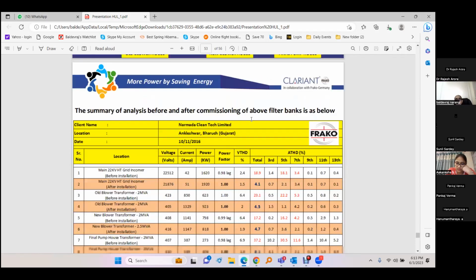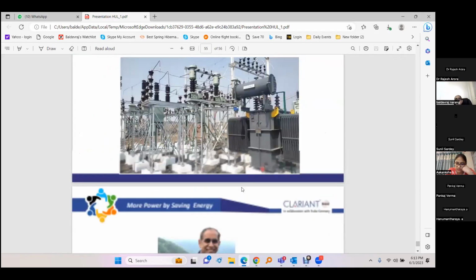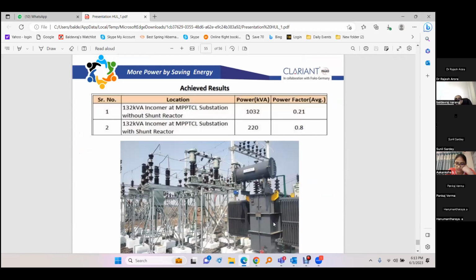These are again some similar examples for other plants. This is one solar installation. We have given a solution. It is again an 800 kVAR shunt reactor and one STATCOM in the substation. It was in MP, and they were being charged a very heavy penalty because the power factor was about, again, 0.1, 0.2 leading. Their own consumption was just 100 kilowatts or something for their in-house requirements, and the demand was shooting up to almost 10 times. So this is the demand, and this is the power factor. And they used to pay 60, 70 lakhs of penalty every month.